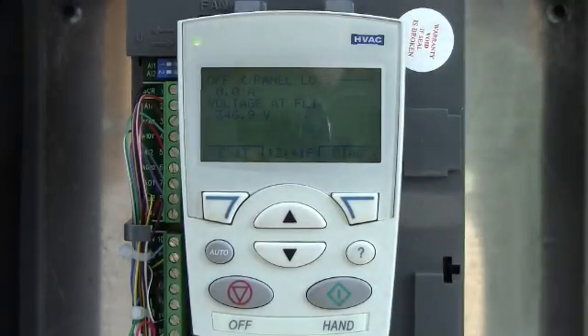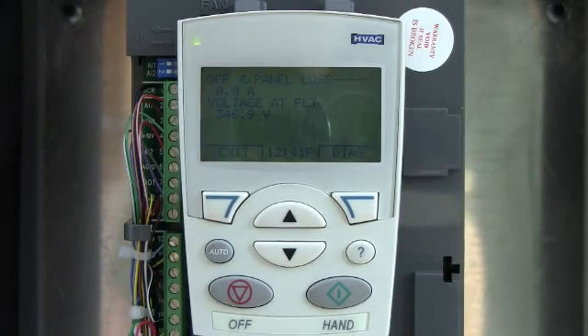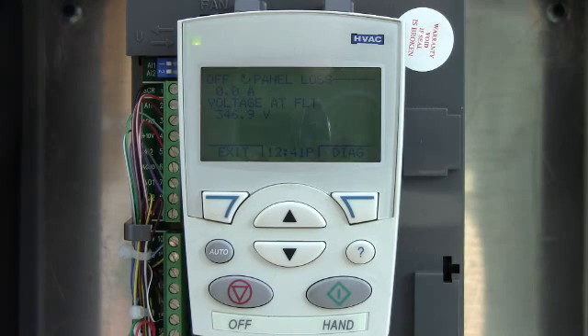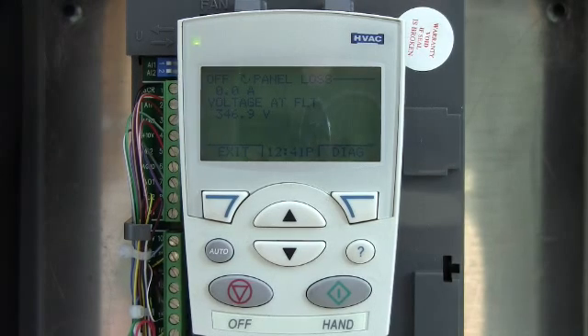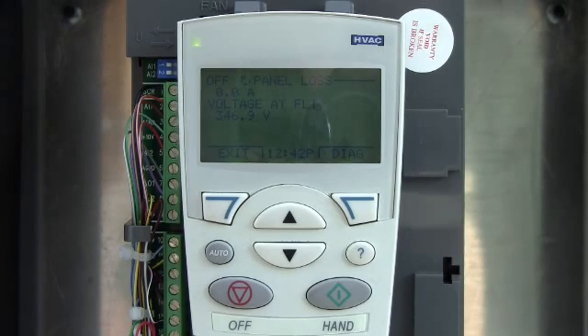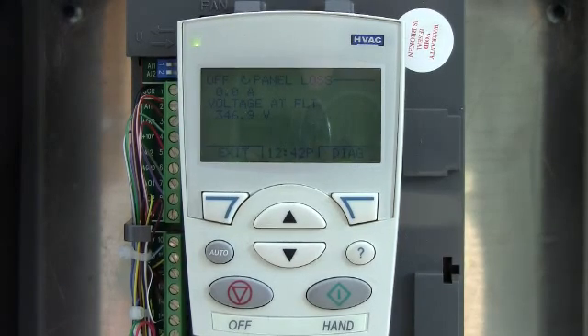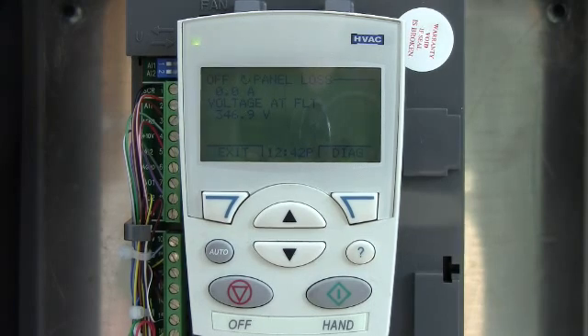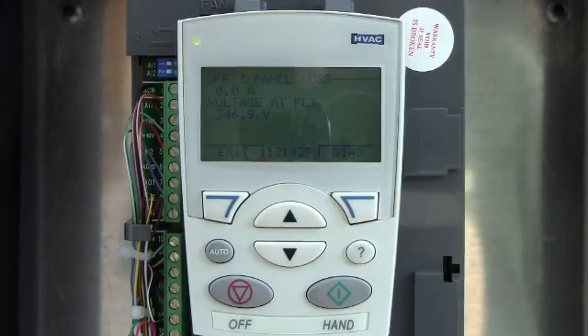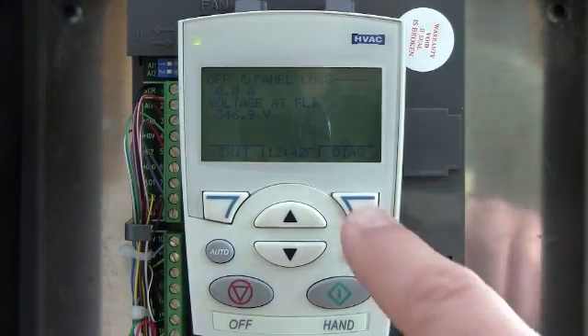What's handy about that is if the drive had something a little more substantial — let's say an overcurrent trip — you could actually look and see at what point the drive was running in the speed range. Was it running at 50 percent speed when it tripped? Was it a hard trip or was it a real high current spike? Those types of bits of information can help troubleshoot the drive. Wanted to point that out for you.